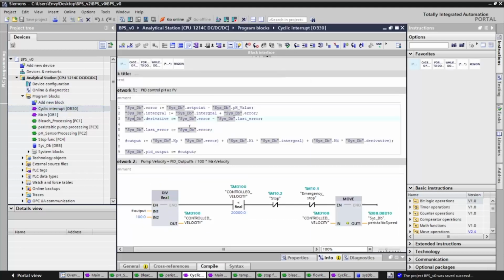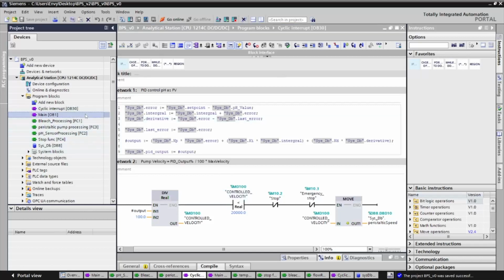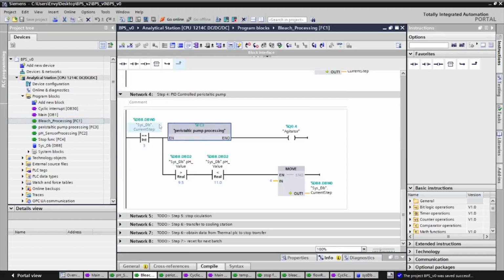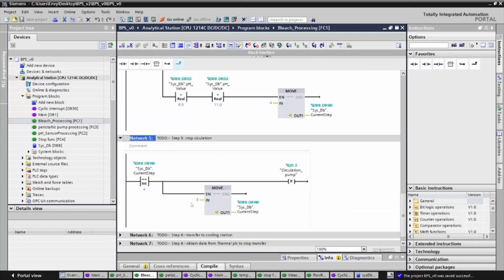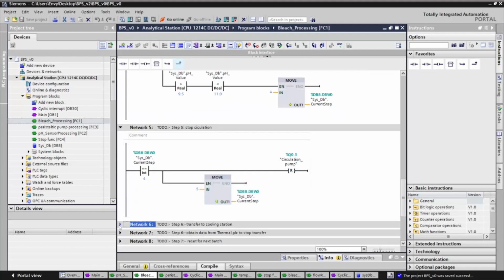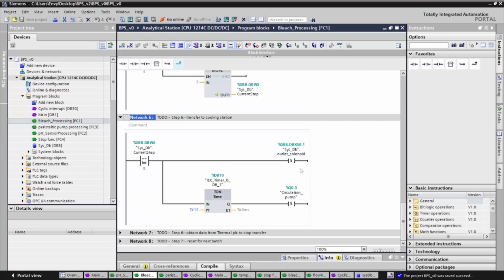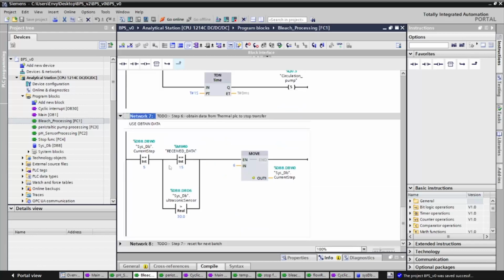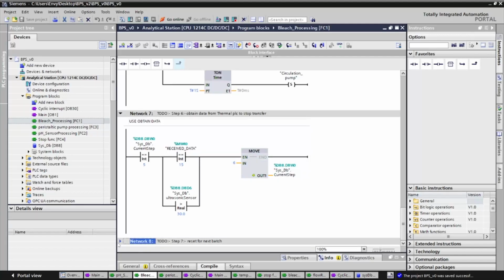Here's the logic. The essence of the peristaltic pump is to pump in the concentrated calcium hypochlorite solution in order to monitor, reduce the concentration and regulate it to a pH of around 9 to 11. Once the required set point is reached, we stop the circulation and start the transferring of the bleach into the thermal station. On this network, I receive information from the PLC that the transfer has been completed, and this is used to stop the transfer, and we reset for the next batch.